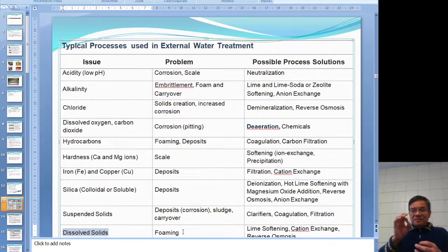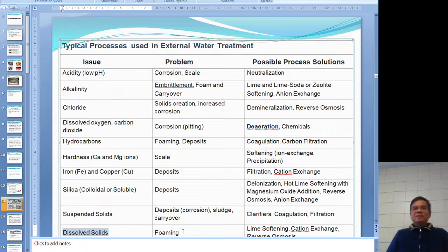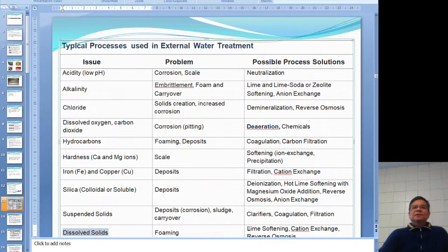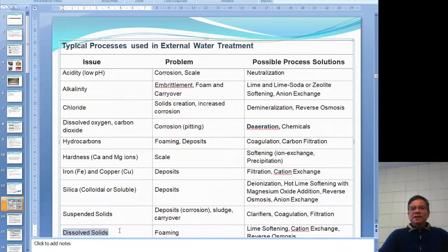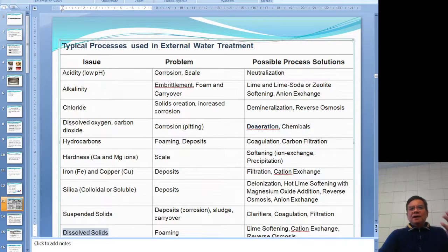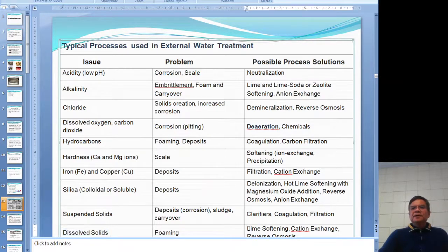Carry over doesn't have to be mineral — it can also be water droplets. Water droplets hitting the turbine will cause imbalance. To address dissolved solids: water hardness and total dissolved solids are the major concerns. Use a water softener and reverse osmosis to handle these.